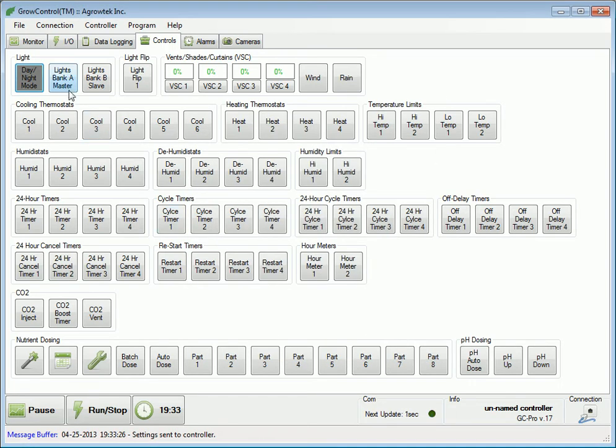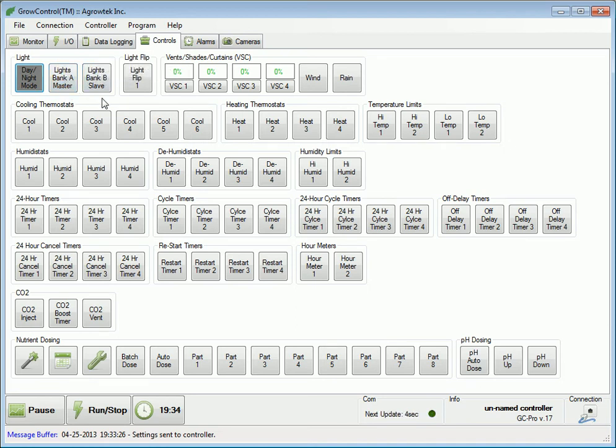Lighting timers are divided into an A and a B bank. The A bank contains the 24-hour on and off timer, and the B bank is a delay timer which operates after the A bank has been activated. This allows splitting your lights into two zones to reduce electrical loads. The B bank output can also be used to control any other device that should be operated when the lights are on or after the lights come on.